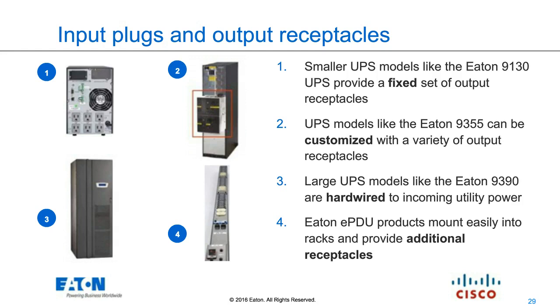Then the other thing to think about when powering network switches is if you're using voice over IP phones and power over Ethernet for those phones. That can add additional considerations to UPS runtime that you need to think about, especially if you expect people to continue working and use a phone or even make emergency calls. If everything's going to be voice over IP and power over Ethernet powered, you really need to start looking at extended run times. You don't want to be holding up those phones for just 5 minutes—you want to think about how many hours you can hold them up.